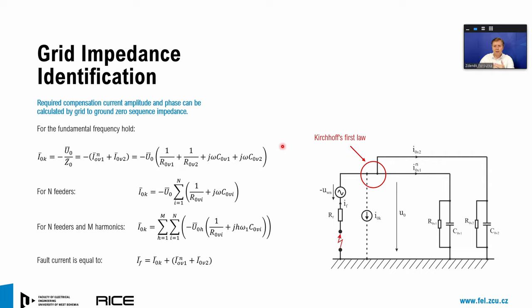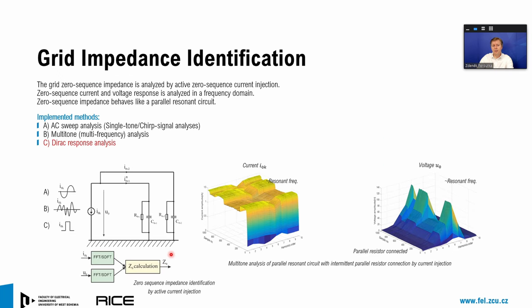The idea is very simple, but the problem is how to calculate the compensation current. The compensation current can be calculated from Kirchhoff's current law in this node. And if we have a look at the circuit configuration, the compensation current can be derived from the known or measurable zero sequence voltage and the grid impedance. So if we know the grid impedance, then we are able to calculate the compensation current generally for N feeders and M harmonics. And the fault current is equal to the compensation current plus the zero sequence current of all N feeders in the system. The problem is how to identify the grid impedance.